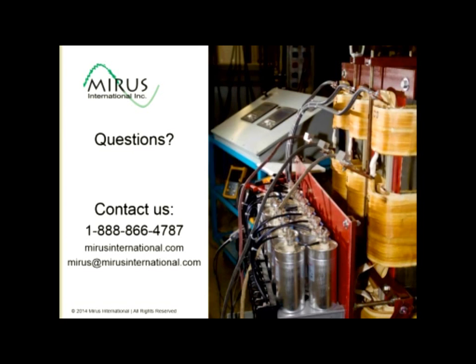You indicated that harmonic content affects power factor. Am I correct that at light loads the harmonic is mathematically greater than the VFD, but has less demand distortion and therefore less of a power factor impact? It is true that the percent THD will go up under lighter loading, but the actual harmonic currents in RMS value will be lower than they are when you're at higher loading levels. So the result is less of an impact on the power system. The harmonic components will lower the power factor, but at lighter loads it's not as much of a problem on the power system.